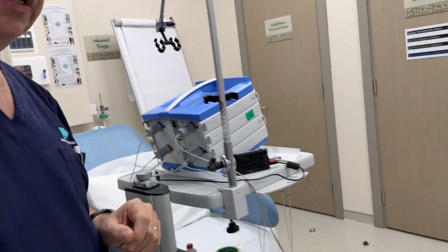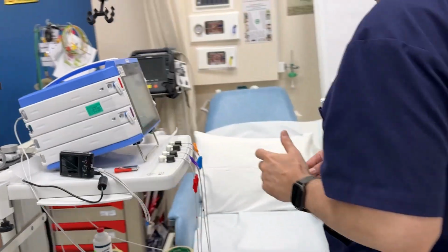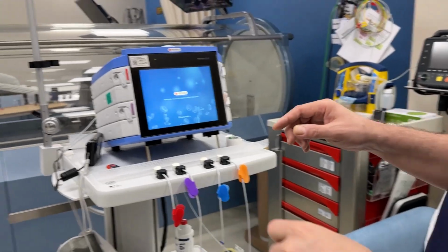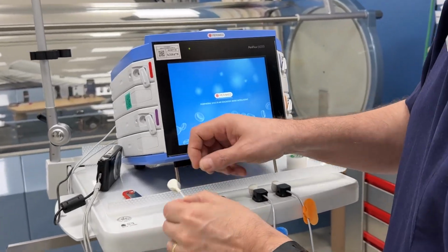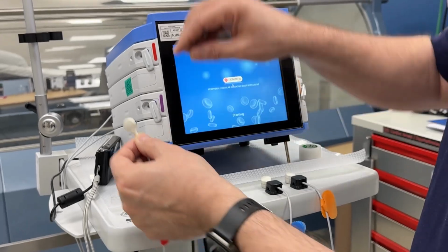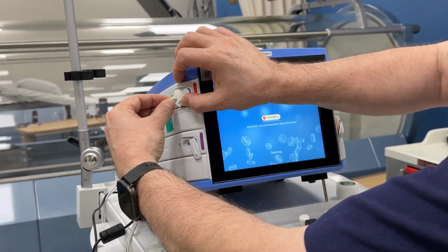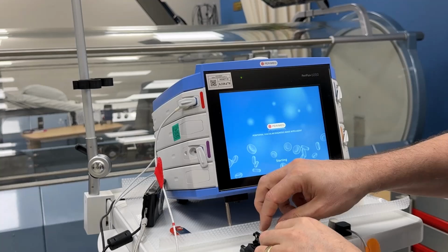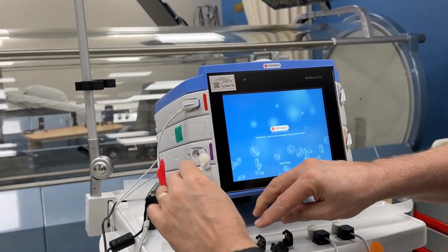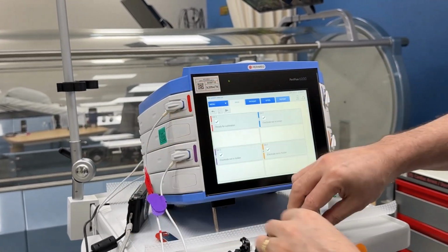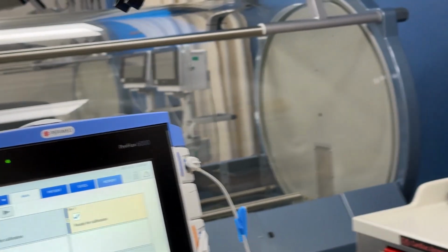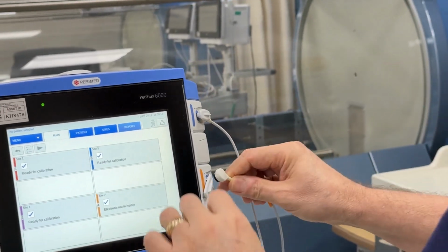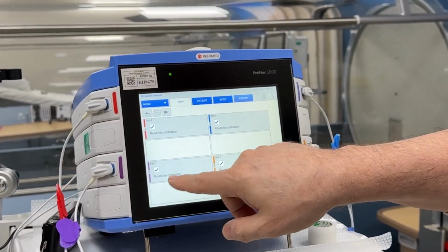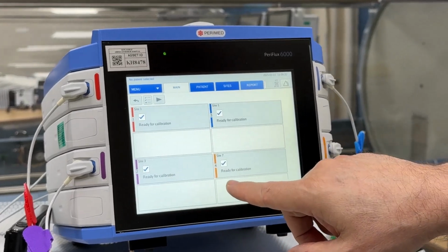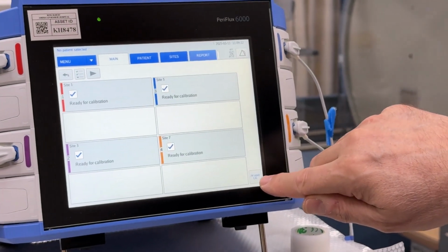So at this stage, the TCOM should have started up, and the first step is to take the electrodes, remove the cap, place them in the docking station, and swivel it so that they're secure in position. So we're going to do that with each one of the 4 electrodes. Here we go. And the last one. You'll notice that on the screen it shows that all of the electrodes are checked and ready for calibration. And here it says calibration button.